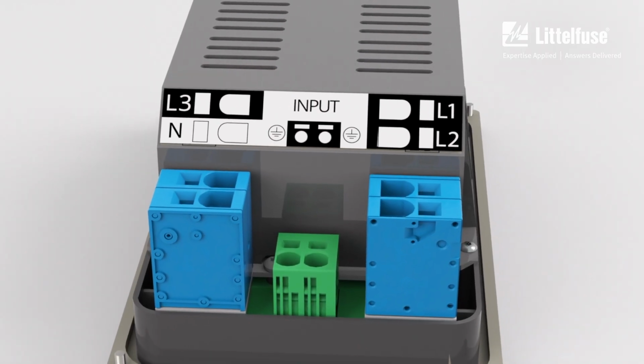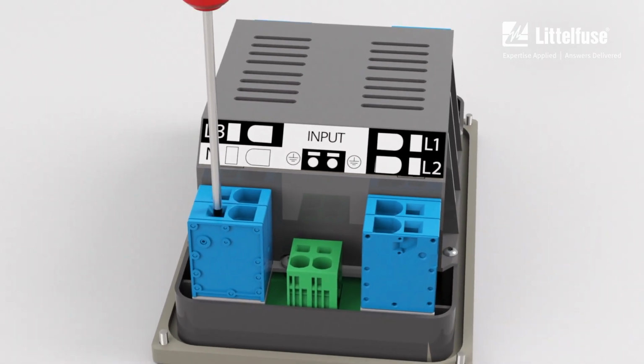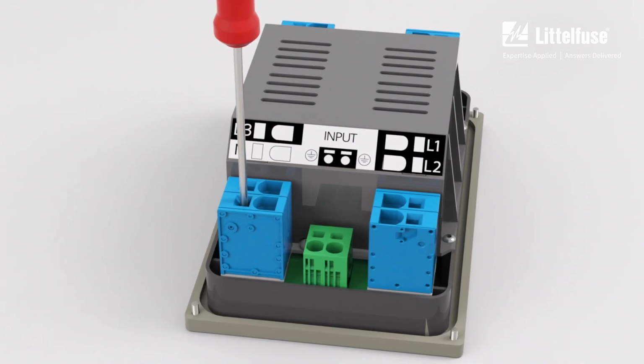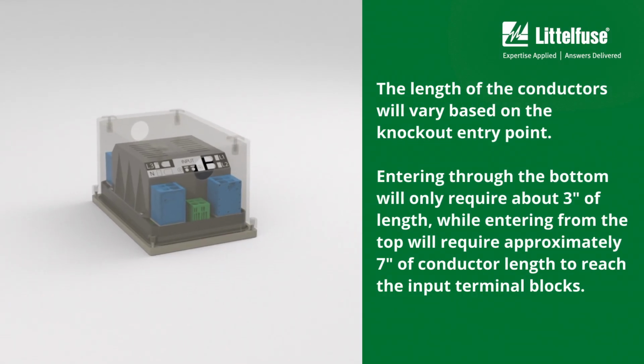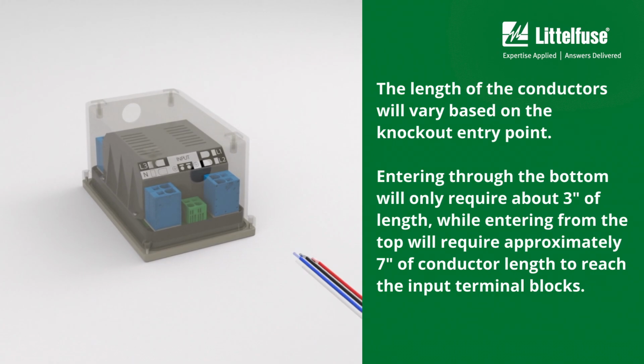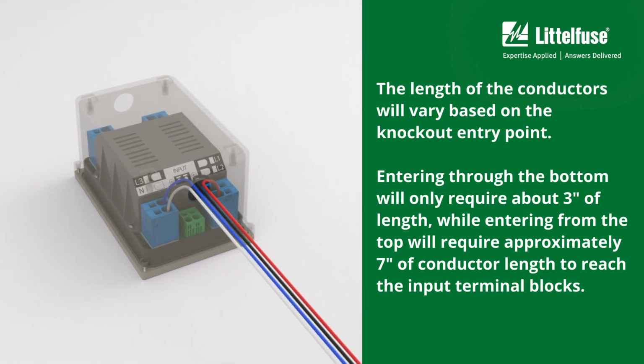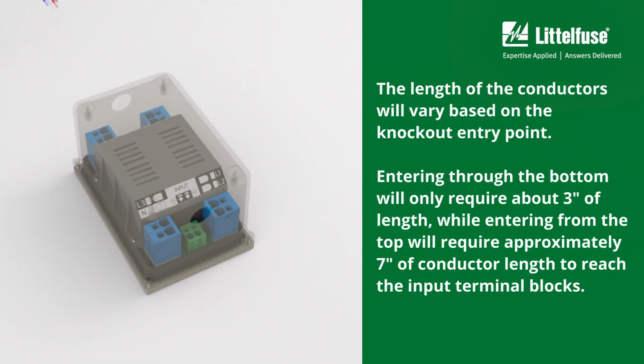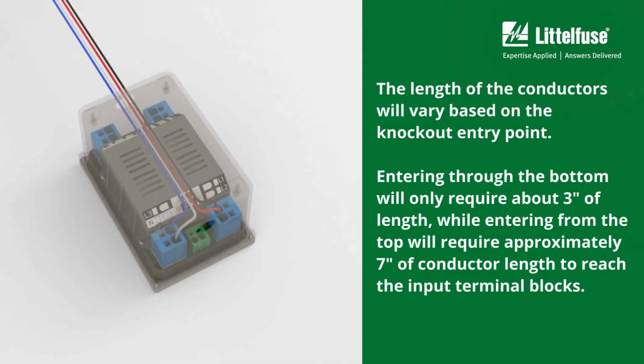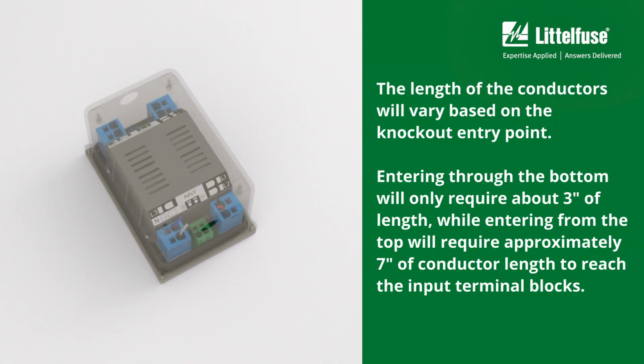Use a small flat screwdriver blade to release the tension on the terminal block for inserting or removing conductors. The length of the conductors will vary based on the knockout entry point. Entering through the bottom will only require about 3 inches of length, while entering from the top will require approximately 7 inches of conductor length to reach the input terminal blocks.